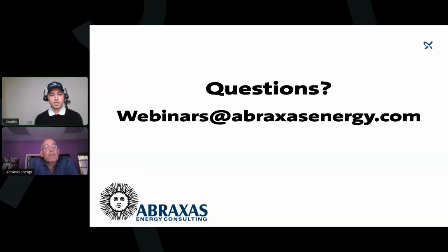Very good question. Yes, you're spot on. You want to select your equipment based on the highest consumption, right, demand. That's when you want to have your highest efficiency. But again, what we are also talking about is increasing modularity. So you're not sizing one pump that is going to have only the highest efficiency there, but then not going to get to the 100% anymore. You want to be able to achieve those peak demands. The difference is now you're getting out of the range there, right? Because you only expect to spend 1% of the time there.